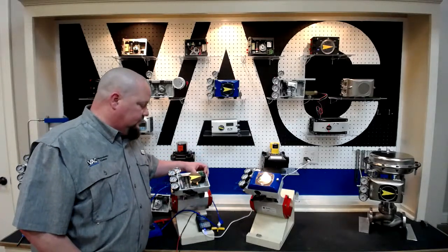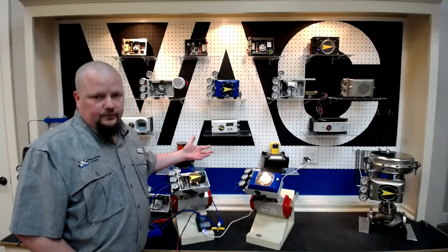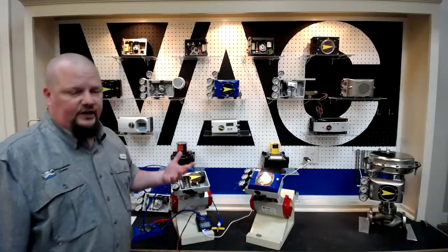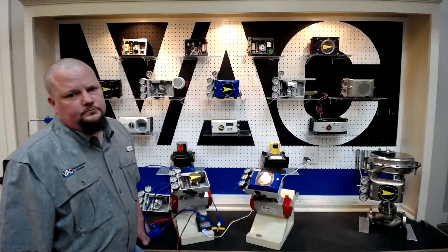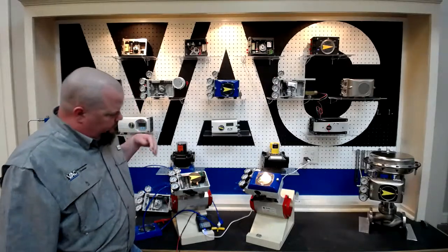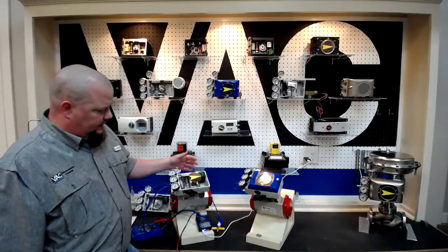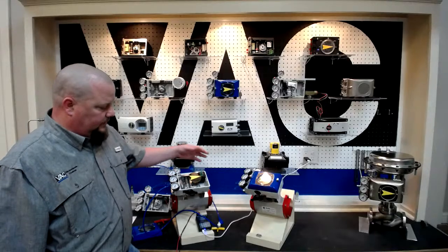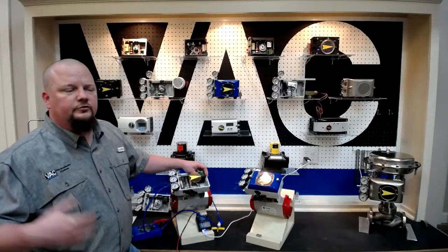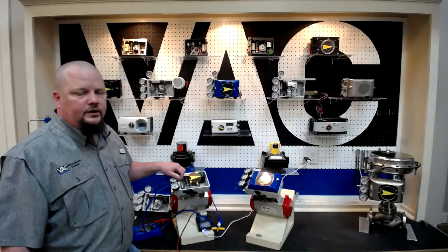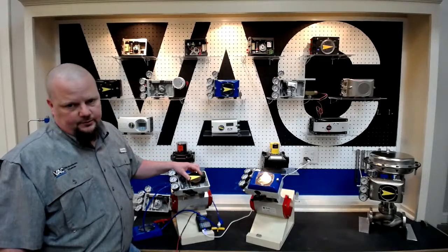The other option, which is generally what I like to do a lot, is to remove it from the system and then use a handheld. Leading back into the general setup issues, the problem is because we don't have a signal generator giving the correct signal, or we don't see supply pressure, or it's a setup issue.